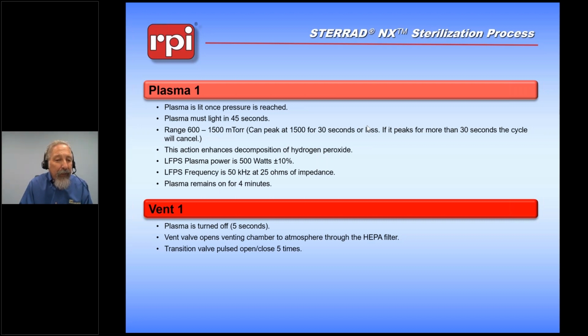The plasma power supply delivers at 500 watts, and it will remain on for 4 minutes. Once that 4 minutes is up and we feel fairly confident that we have broken the bonds within the hydrogen peroxide, so that we have released all possible free oxygen and produced all possible water, we will then vent the chamber to air and allow filtered air through a HEPA filter.